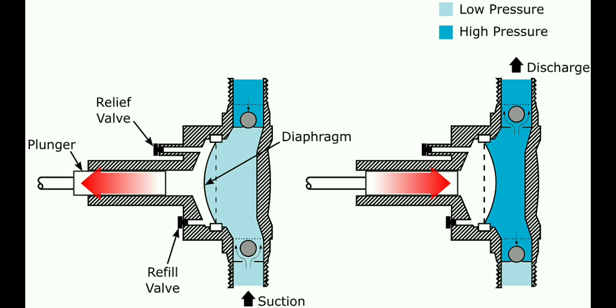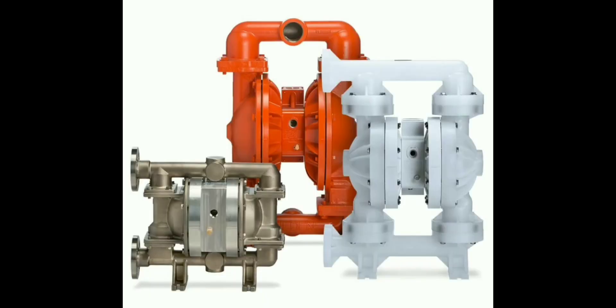Let us look at the disadvantages of a diaphragm pump. A diaphragm pump may have a limitation in terms of high flow rate compared to some other types of pumps. The flexible diaphragm may wear over time, requiring periodic replacement, as prolonged use gives it a high chance of getting damaged. The reciprocating action can result in a pulsating flow, which may not be suitable for all applications.